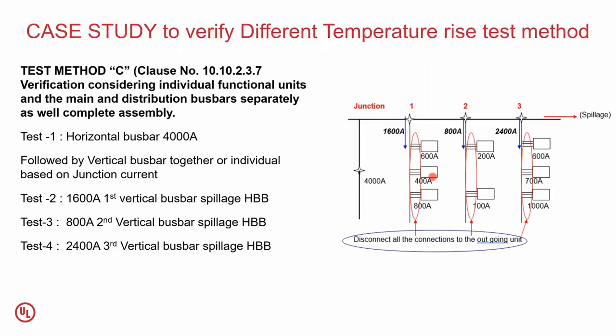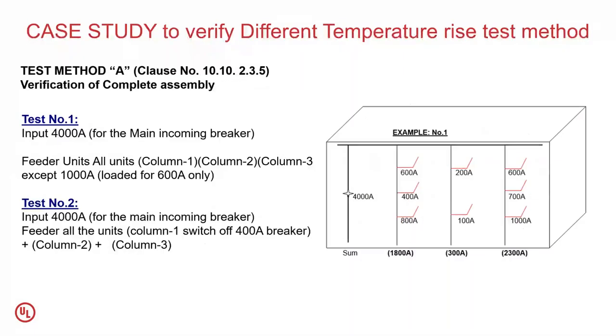If the manufacturer declares vertical also, we are going to test with whatever declared current. For example, here the manufacturer declared 1600 amps, 800 amps, 2400 amps as the vertical rating. These three are also going to be tested individually or together, depending upon manufacturer acceptability.